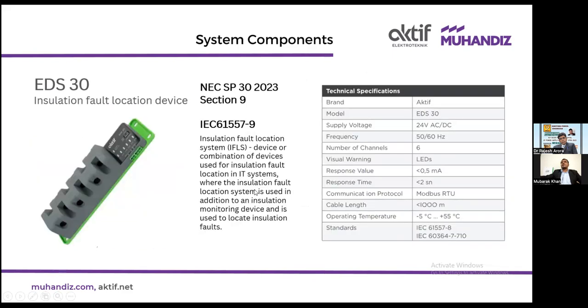And this is an EDS 30 insulation fault location device. This is not mandatory as per the standard, but it is good to have, because if there is a fault, the standard says that you must be able to locate the fault in a very short time. You can do it manually, but it is always better that you get the location of the fault very soon. That is why it is not a mandatory requirement, but it is good to have.